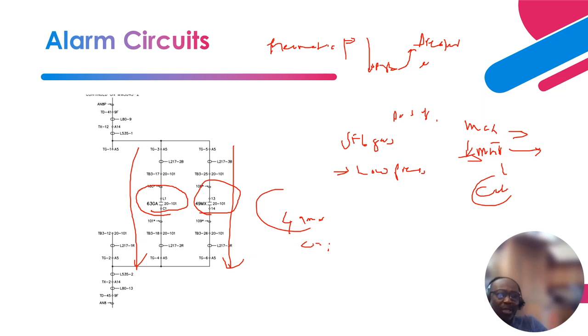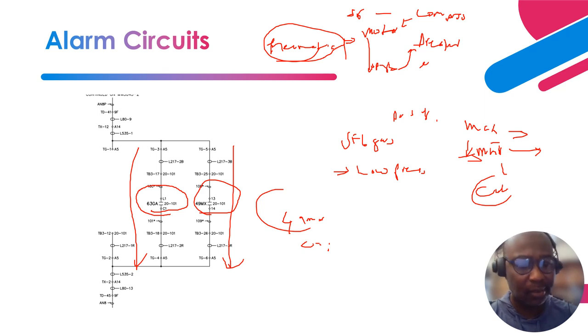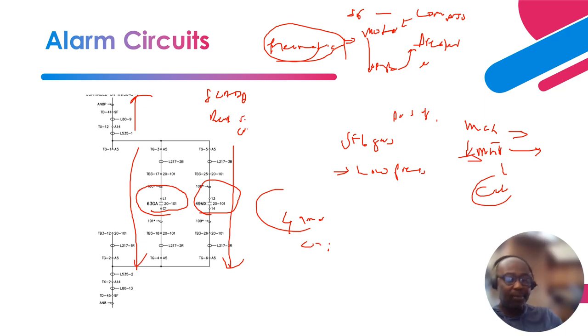If it is using a pneumatic system, then that is basically a compressor, and a compressor has a motor. So this relay, a thermal management auxiliary relay for the motor, tells you that your motor is running hot, and that gives an alarm to your location, whether SCADA, remote RTU, or control center. It can also be an engineering console, DCS system, or an annunciator panel indication.